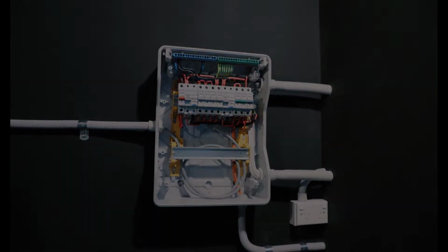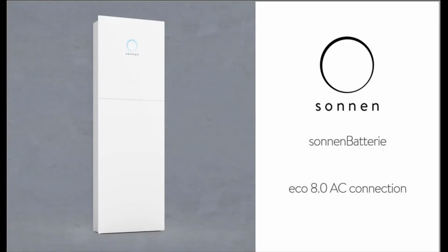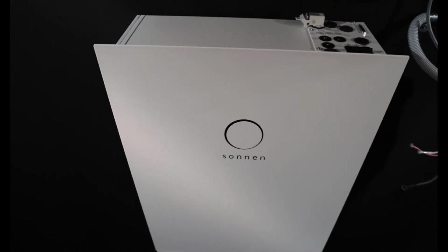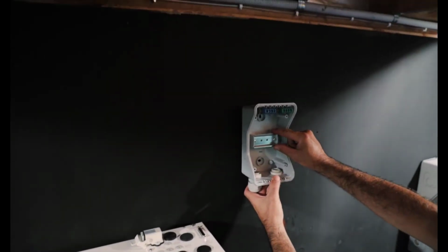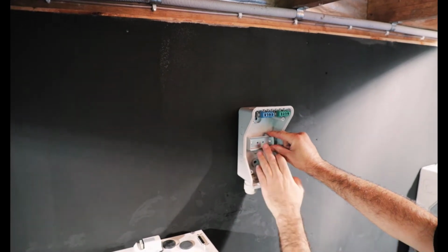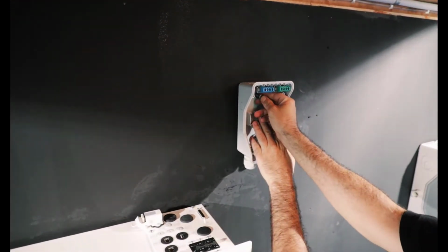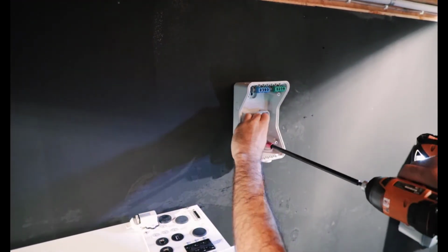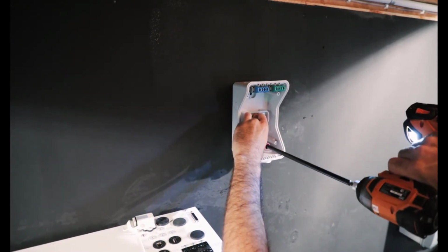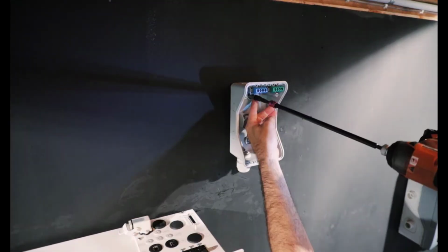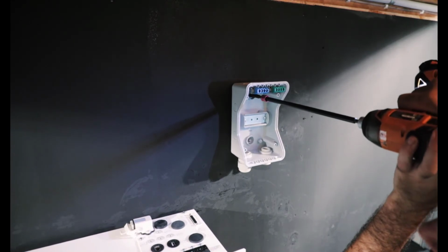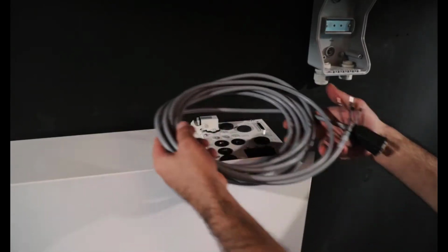Before we get into the details of that setup, we'll just have a quick look at the 3-phase configuration. As you can see, the top of the 3-phase system, the 8.03, has a lot fewer connections. It doesn't have a PV input, so the only real connection you need to worry about other than Modbus and internet is the AC itself. So again, just as with the hybrid 9.53, or with any system, if you're within 3 meters of the switchboard, you don't need to worry about isolation.